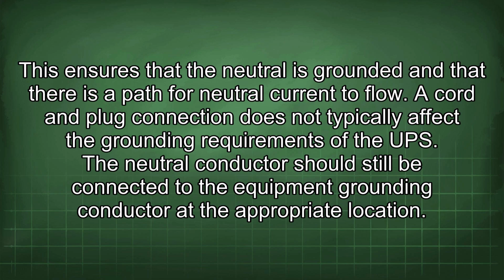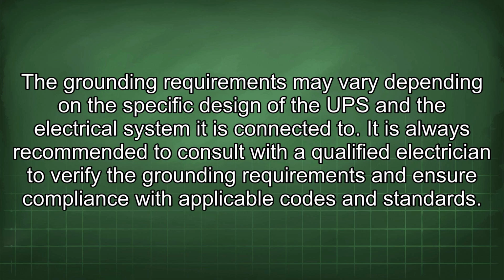A cord and plug connection does not typically affect the grounding requirements of the UPS. The neutral conductor should still be connected to the equipment grounding conductor at the appropriate location. The grounding requirements may vary depending on the specific design of the UPS and the electrical system it is connected to. It is always recommended to consult with a qualified electrician to verify the grounding requirements and ensure compliance with applicable codes and standards.